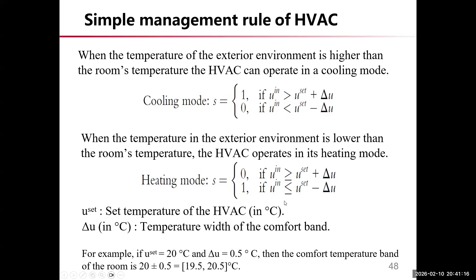Also, for the heating mode, if the temperature is lower than the set temperature minus 1, like 25.5 minus 1, which means 24.5, if it's lower than 24.5, we open the heating mode of the HVAC. And we can set the temperature of the HVAC. Also, we can set the width of the comfort band. Here is a very simple example. It sets the temperature as 20 degrees and the width of the band as 0.5 degrees. So the comfort temperature band of the room would be 19.5 to 20.5. That's the parameter we need to design for the rule of the HVAC.